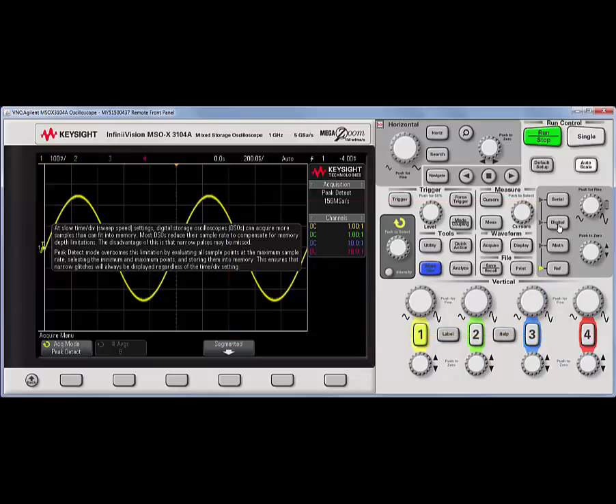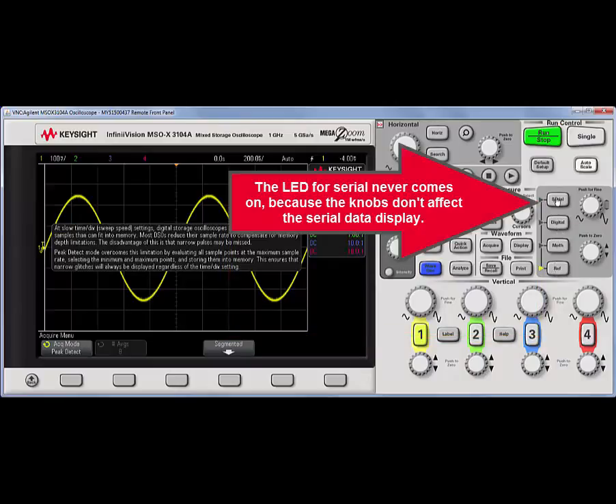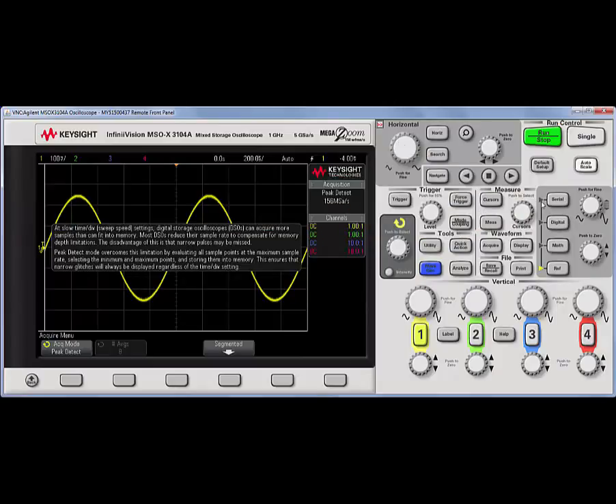The light indicates which of these three knobs or selections is currently being used: digital, math, or reference. These knobs are never used for serial, so this LED never comes on. On the latest 3000XT series, we put in a second dedicated FFT button here and move these serial knobs since this never comes on.